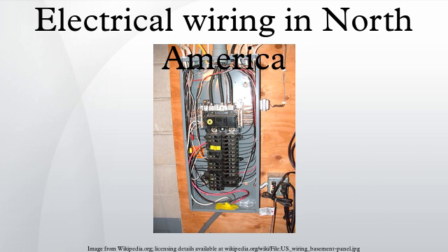With lamp cord wire, the ribbed wire is the neutral, and the smooth wire is the hot. NEC 2008 400.22(F) allows surface marking with ridges, grooves, or white stripes on the surface of lamp cord. With transparent cord, the hot wire is copper-colored, and the neutral is silver-colored. The grounding wire of a circuit may be bare or identified insulated wire of green or having green stripes.